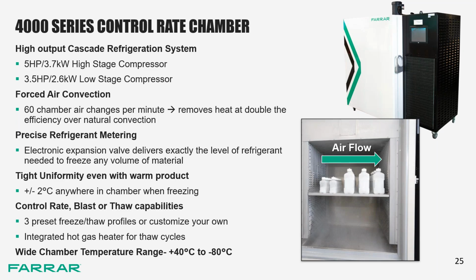The refrigeration system inside this control rate chamber boasts 3 key features that make it one of the fastest, if not the fastest, mechanical blast freezer on the market. Number 1, the high output compressor set. So we have 3.7 kilowatt and 2.6 kilowatt compressors. The best ULTs on the market have just 750 watts or less in each of their compressors. And unlike plate freezers, the control rate chamber can be air cooled, so you don't need to have a chilled water line, and doesn't circulate hazardous silicone oil.